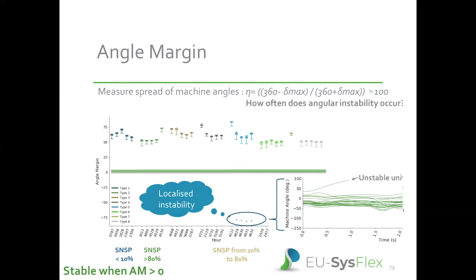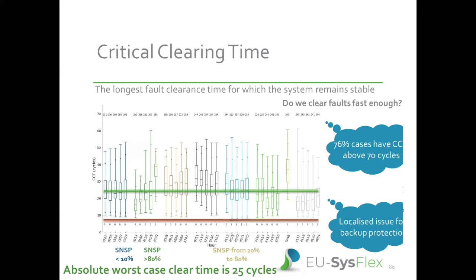Going on to the next slide, which covers critical clearing time. This we found using a binary search. So the red line marks the 8 cycle clearing time, which is our expected clear time. The green line is our worst case backup clear time at 25 cycles. And any clearing time of more than 70 cycles doesn't appear in these box plots. So unlike the other box plots that had all 800 contingencies, this just has the subset of, shall we say, problematic critical clearing times. And you can see we have a localized issue for backup protection. A lot of those boxes are starting to creep down below that green line, and some of them are starting to get a little too close to that red line with their tails. But equally, as you can see on the slide, 76% of the cases have above 70 cycle clear times, so they're absolutely fine. So again, we have a localized issue that isn't necessarily strongly linked to SNSP.